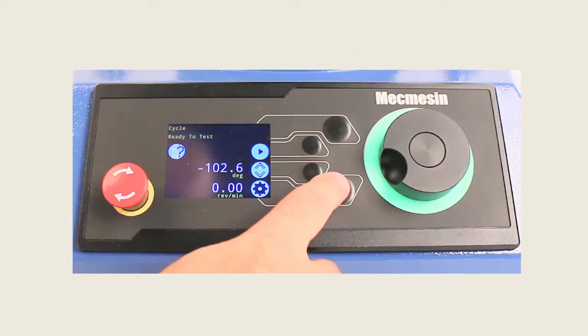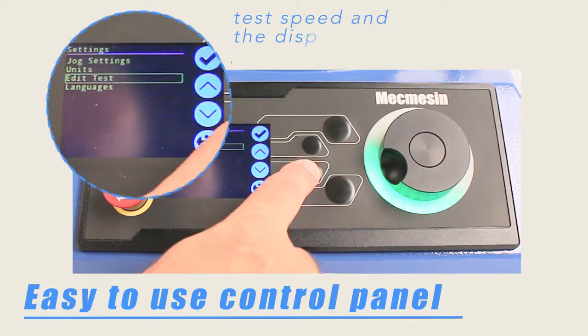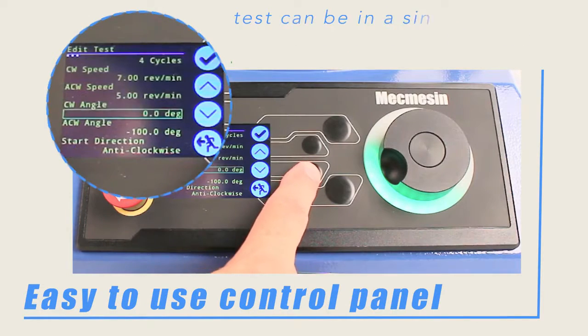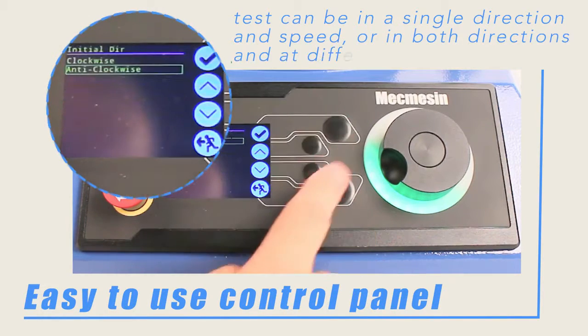The control panel can be used to set and display the test speeds and the displacement in degrees or number of revolutions with digital accuracy. The test can be in a single direction and speed, or in both directions and at different speeds.